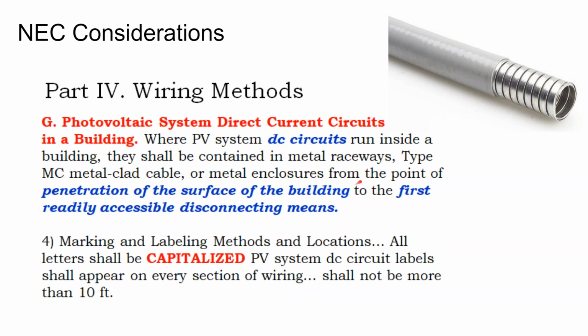This is another thing that starts to explain why these grid-tied battery inverters are so weak, for lack of a better word. There's a requirement that says if you're going to have automatic transfer equipment, whatever your standby source is, it needs to be capable of supplying the full connected load. And so if my battery inverter is like the SolarEdge storage inverter, it's not capable of supplying a 200 amp residential home. It's only capable of supplying 25 amps at 240 volts.